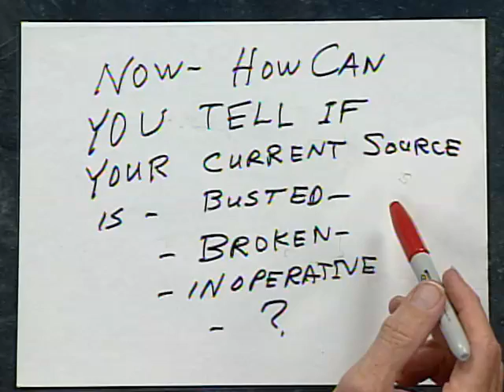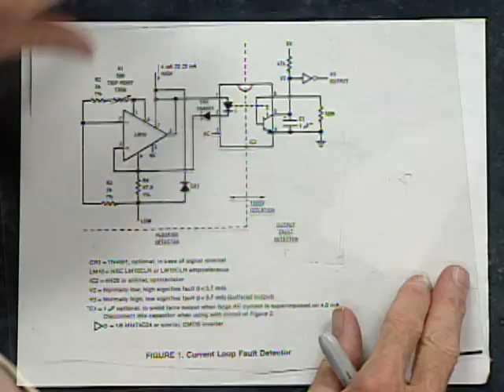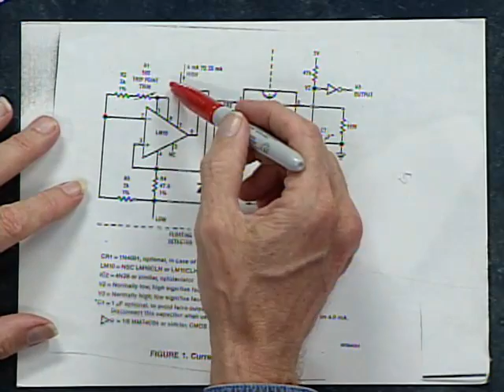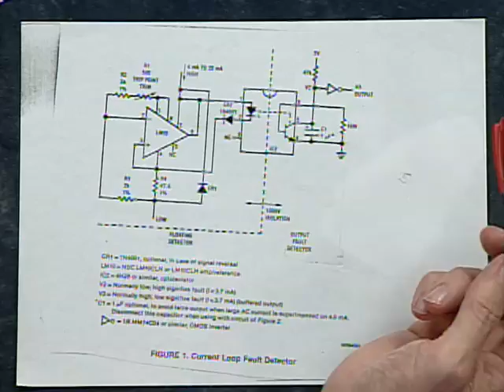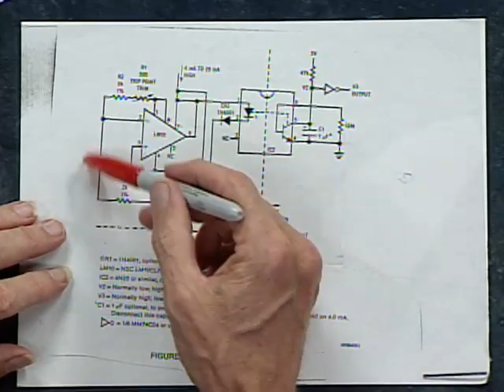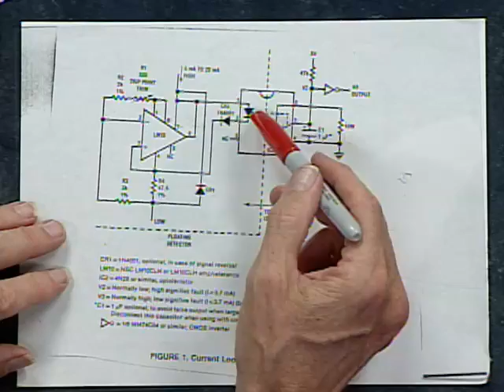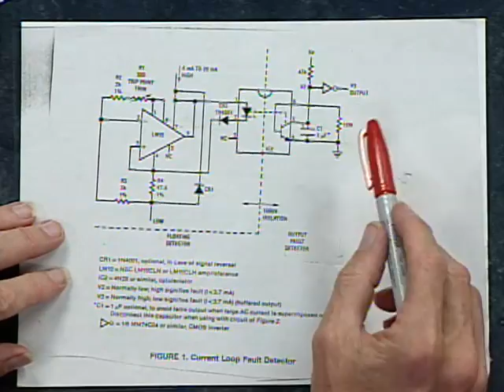We've got AN300. When we first published this circuit in Instruments and Control Systems, they said this was the most popular, voted-for circuit they'd had in many years. You have a current, it's either 4 milliamperes or 20 milliamperes or somewhere in the middle. What if it's 3 milliamperes? The LM10 says there's a problem. This IR drop is wrong. I'm going to change the current through the optocoupler, which then signals it's busted.